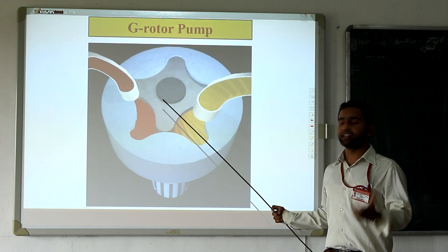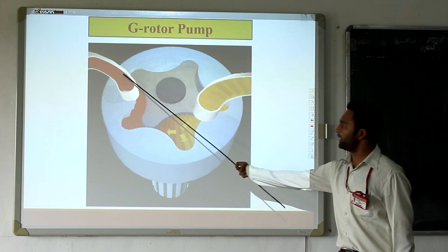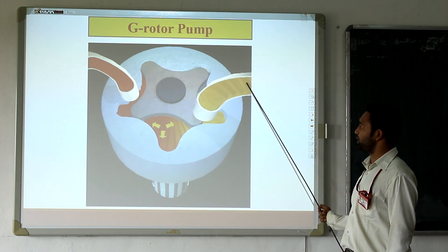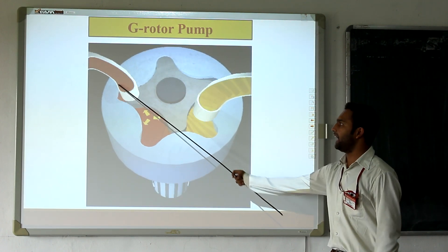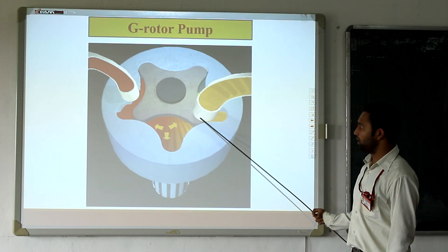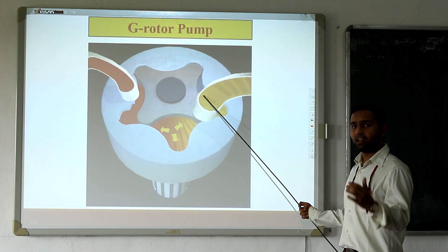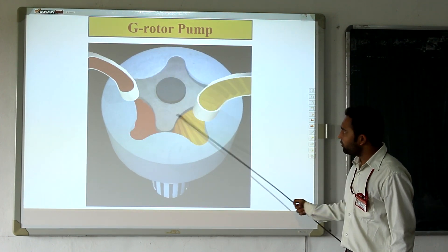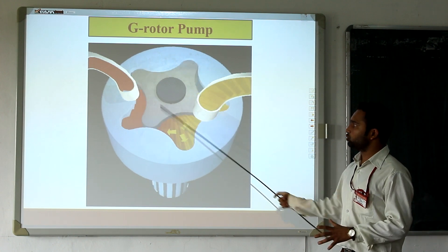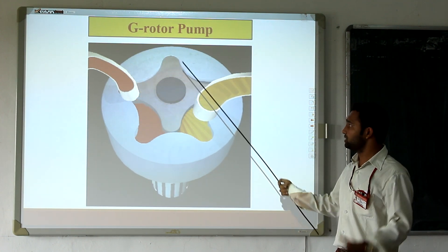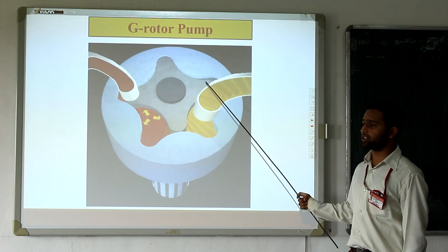Gerotor pump is also a type of gear pump. Basically, suction is possible from one side and this is the discharge side. Red indicates suction and yellow indicates discharge. Suction is possible because area increases, pressure decreases, and fluid moves towards the inner side of this gear. Similarly, at the outer side, whenever area decreases, pressure increases and discharge is generated. In case of this inner gear, there are four teeth, and the outer gear has five grooves. So we can consider the outer teeth having N numbers and the inner teeth having N-1 numbers of grooves and teeth. This is the basic construction of the gerotor pump.